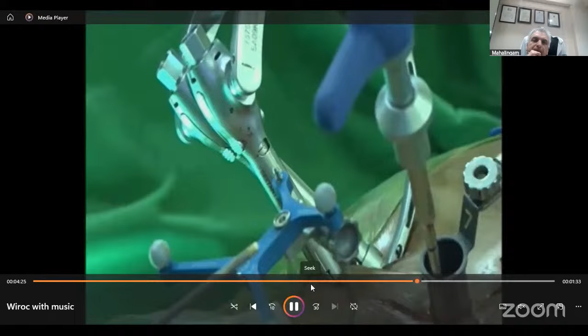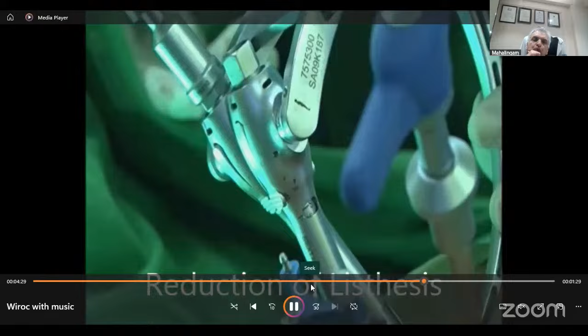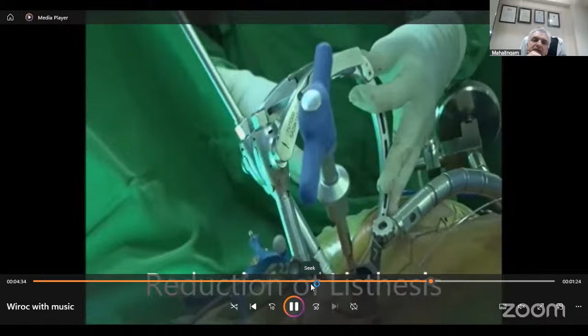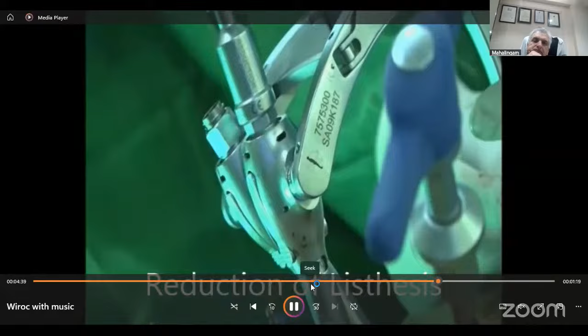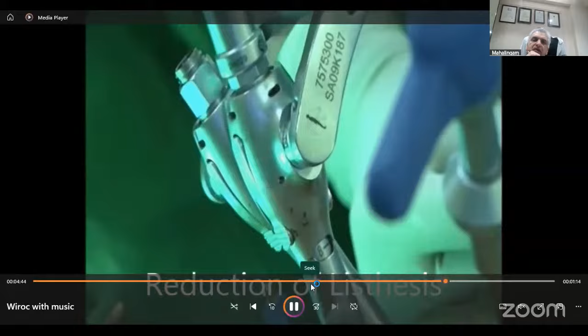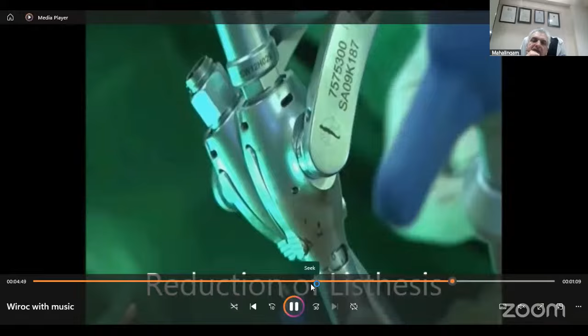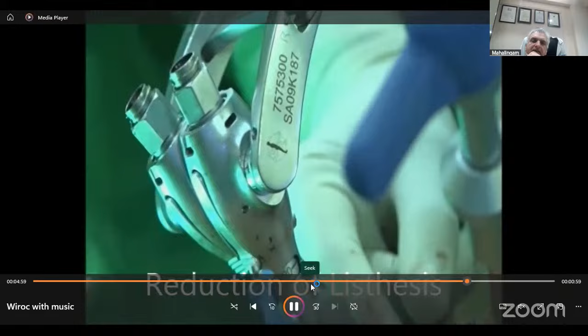By tightening the reduction screw mechanism, you can pull the L5 back on S1. At the same time, you're manipulating the disc height with the shavers on the ipsilateral side. If you look at the C-arm image, you can see a sudden correction in the degree of listhesis.